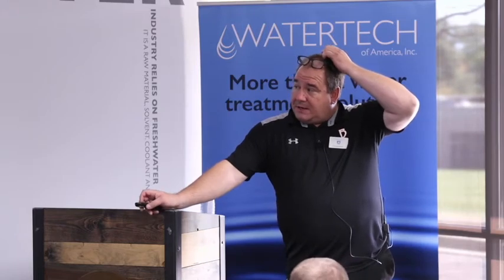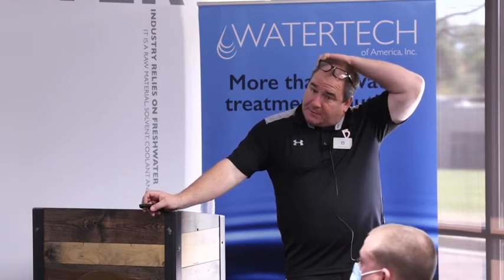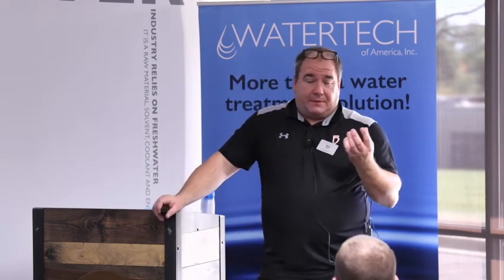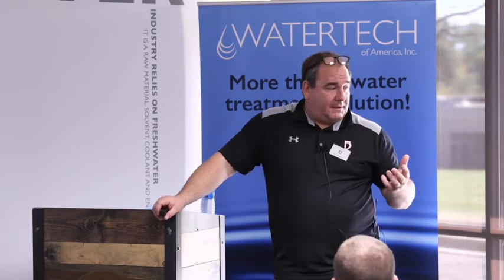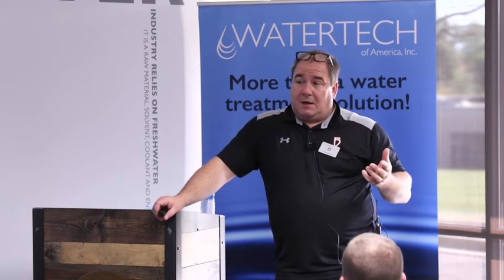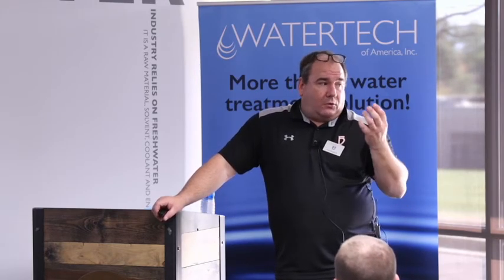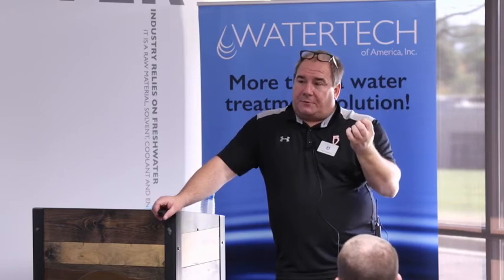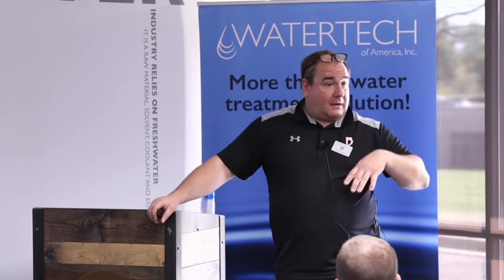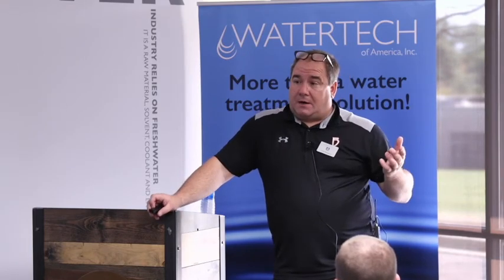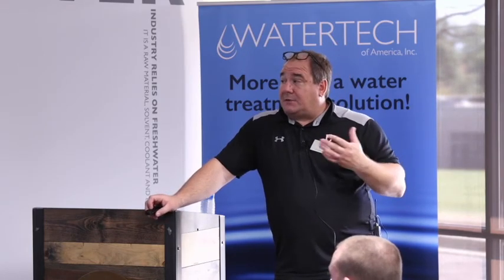Or what it could be is you could have a poor spray pattern. So remember on that one picture it showed you where that one column was, we call it the tray or the spray pad in the location. So depending on what it is, you could have nozzles that are clogged in there that aren't allowing the spray to create the surface area to drive off the air or the oxygen. Or your trays could be clogged, because there are holes in the trays to allow the water to fall through from one tray to another, because you're trying to increase the surface area to allow the oxygen and the air to escape out of the water, right? The gases. So you could also have spray patterns.